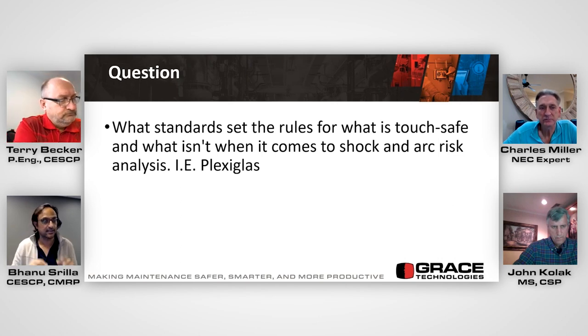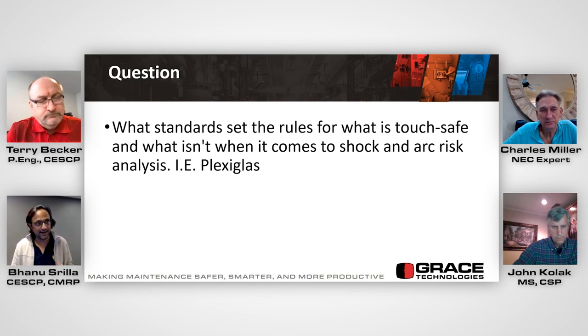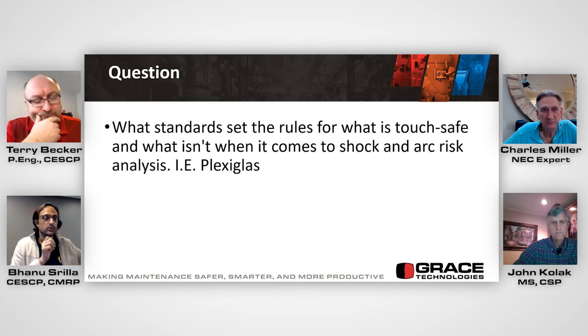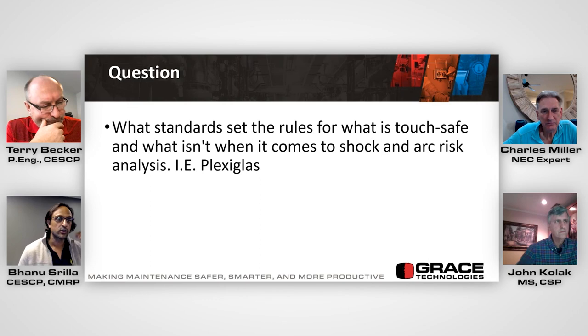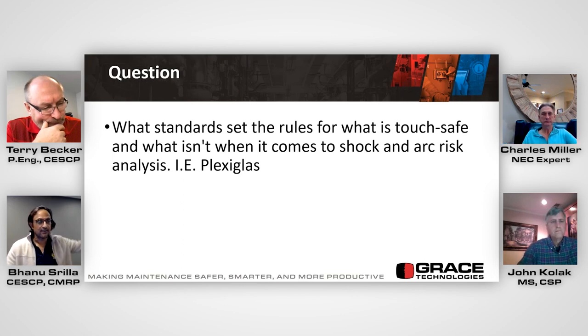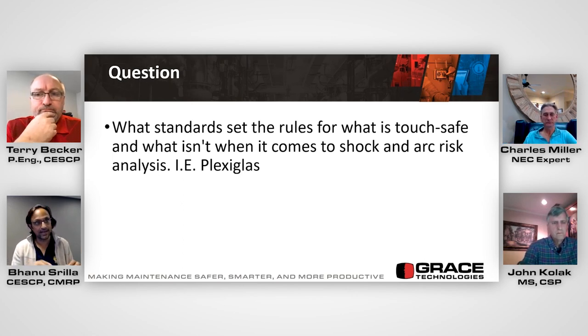They can't access it. The question was, then why do you call this a Cat 3 and Cat 4 meter requirement? So I want to clarify, the Cat 3 and Cat 4 ratings on the probes apply to the actual point of test if you're doing it inside the cabinet, meaning if you're touching live conductors and measuring inside the cabinet where your source is connected.